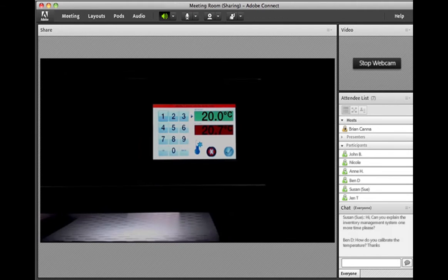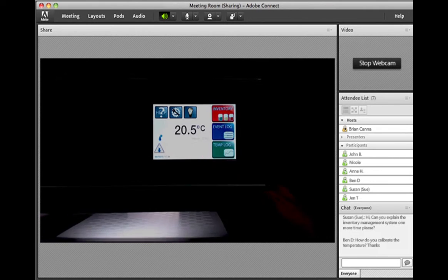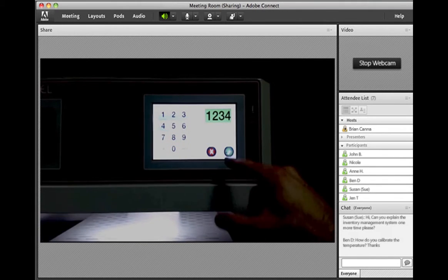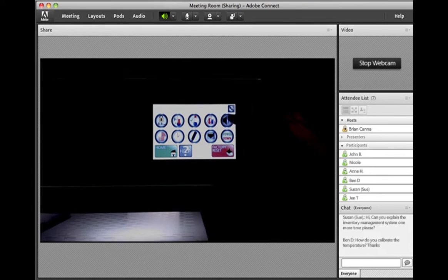Now this is a 2-point calibration, and we're able to maintain very tight accuracy on the system because the window of control is so small. Since we're just trying to maintain that 22 degrees C temperature set point, we can be very accurate, and that's indicated by some of our graphs. See, right now the low temperature alarm went off because it's trying to calibrate. So I recommend, if you're going to calibrate the temperatures, that you actually shut off the speaker like that, and then you won't have nuisance alarms, and then just make sure to turn it back on.